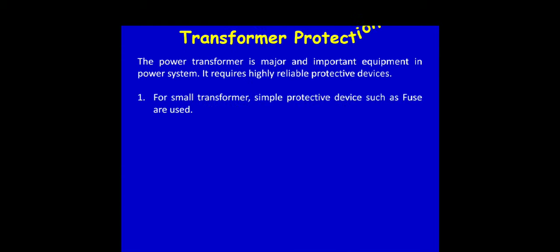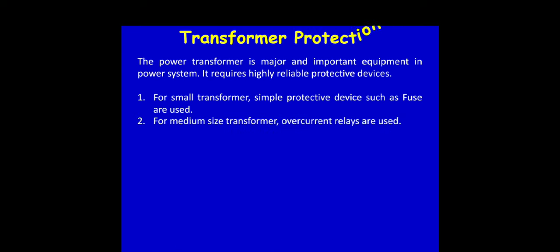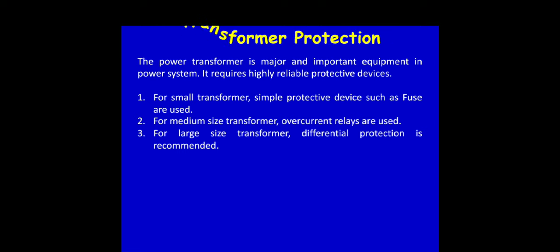First we have to discuss the transformer protection. As we know that the power transformer is the major equipment, so its protection is required, requiring highly reliable protective devices. Small transformers require simple protective devices such as fuses. For medium-sized transformers, overcurrent relays are used, and for large-size transformers, differential protection is recommended.